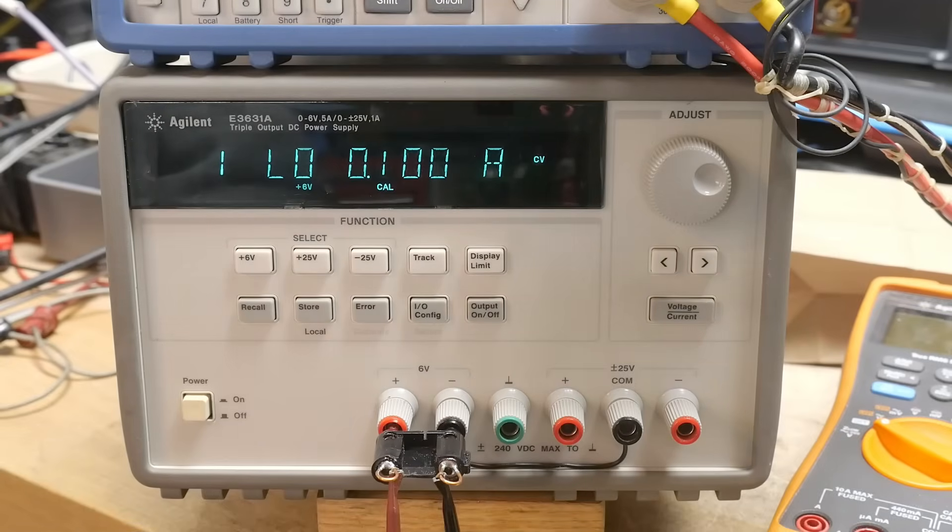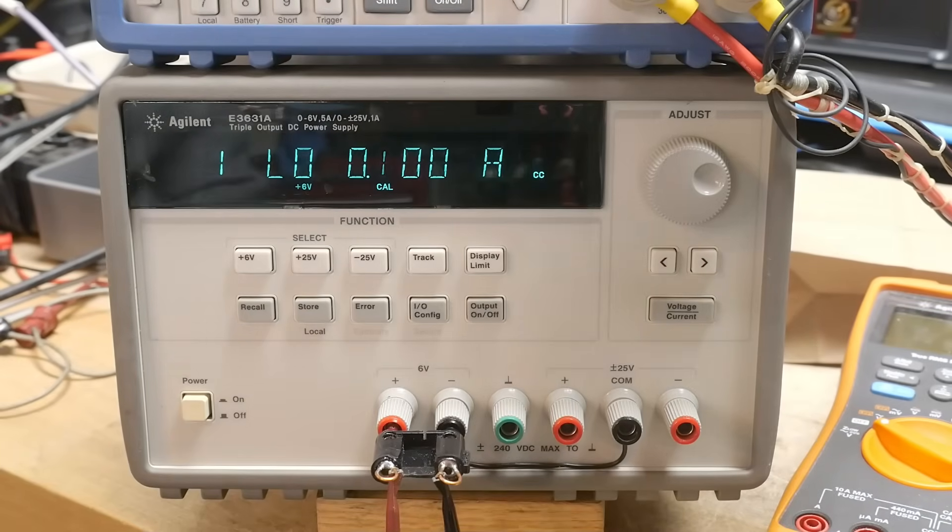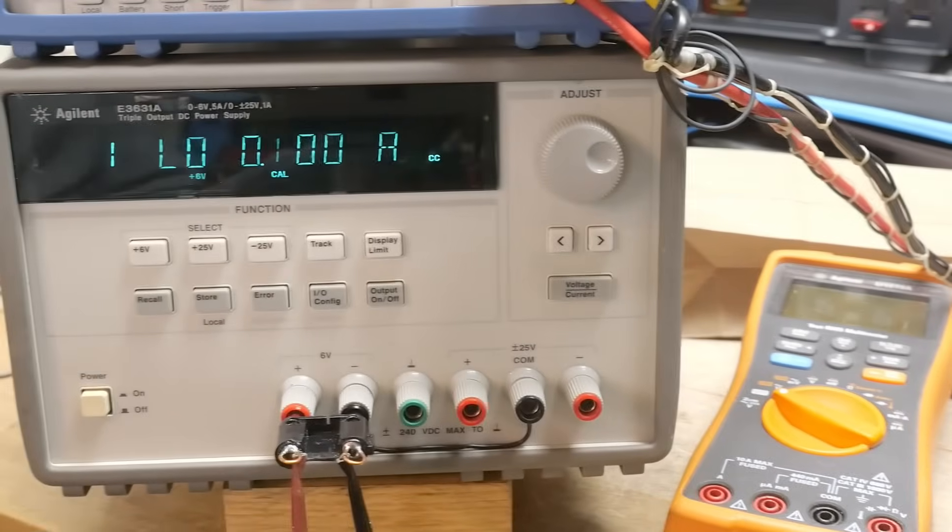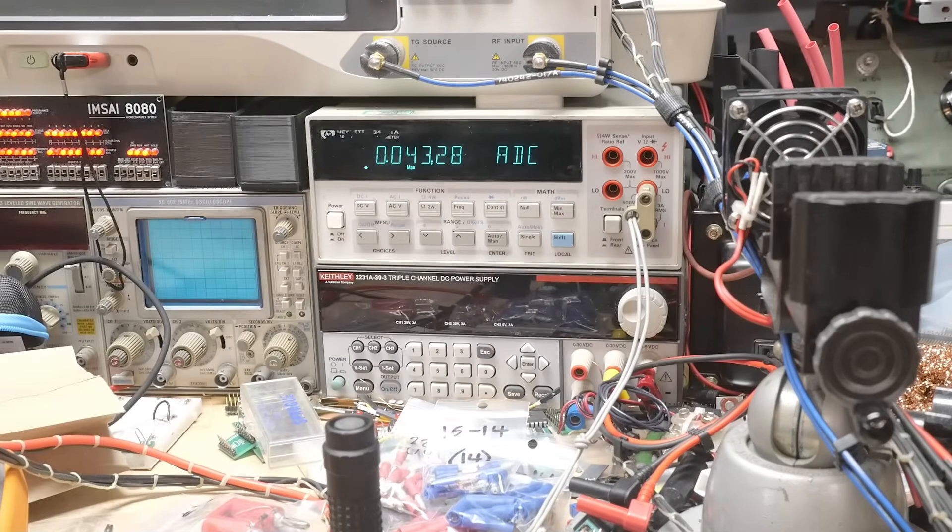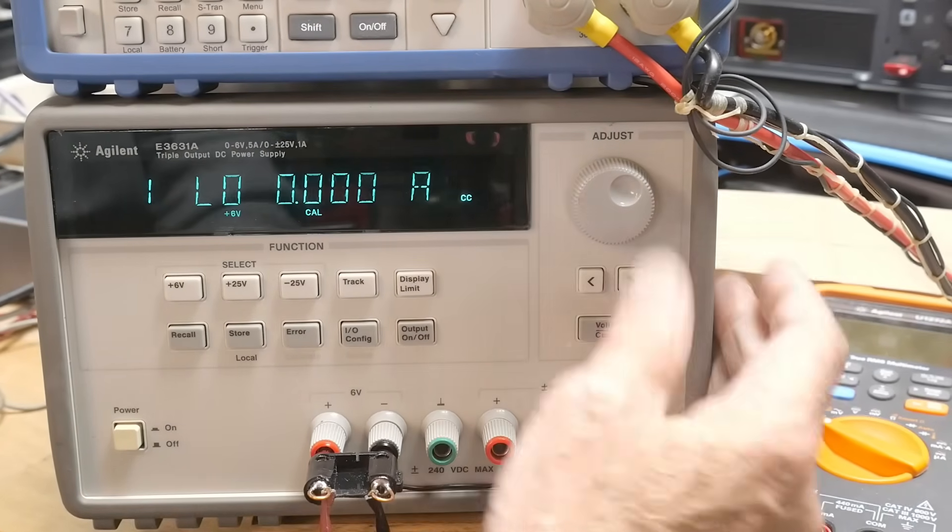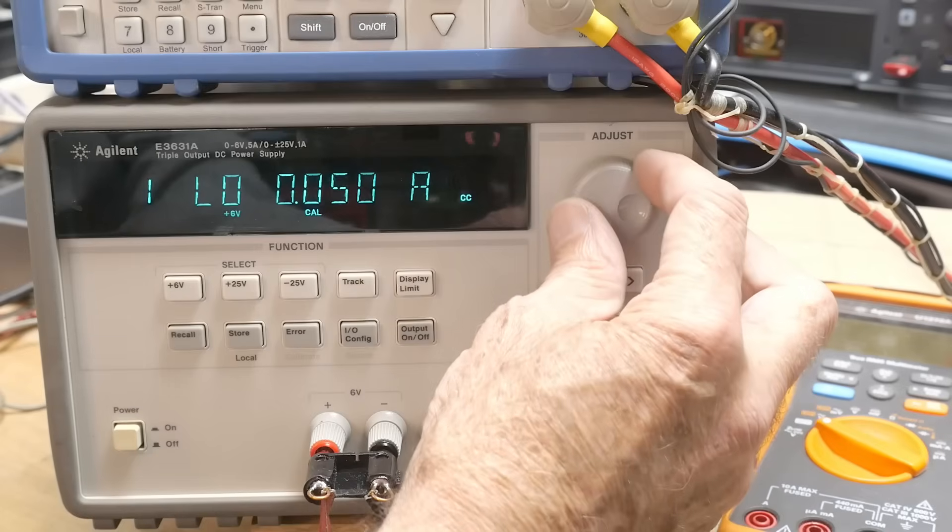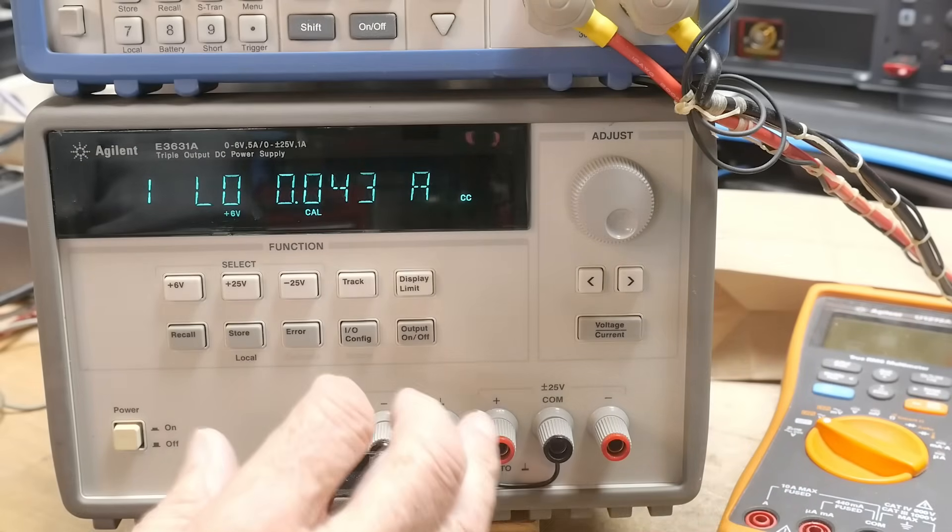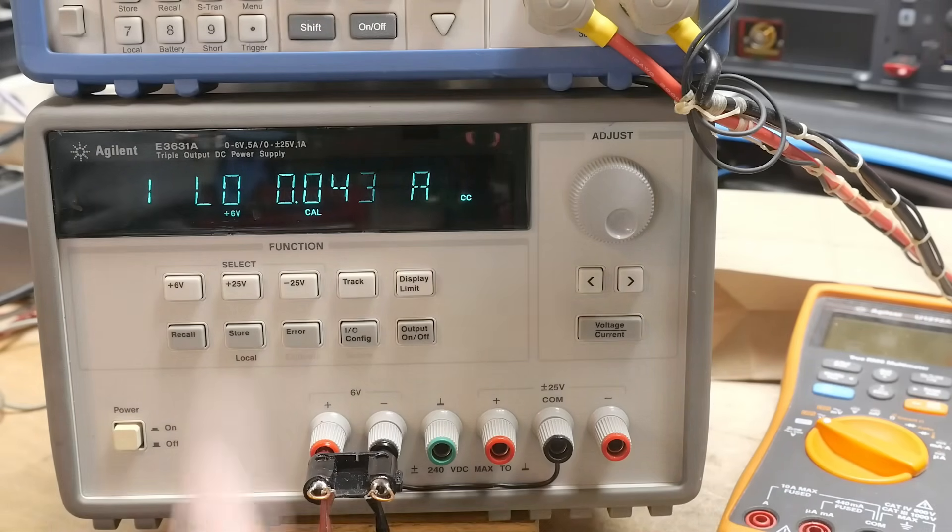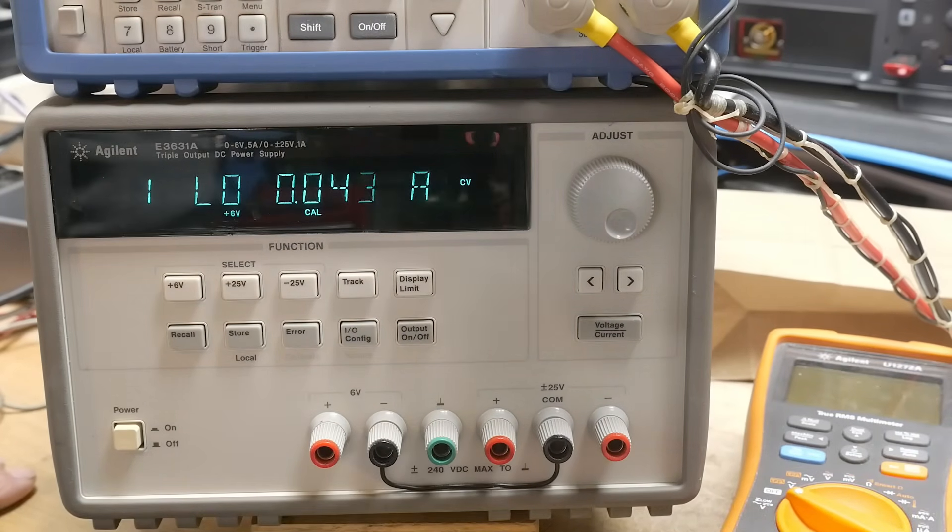Now it's going to output current. I'm going to have to reach around the camera here. I've set my meter over there to current. So it's a hundred milliamps and we're actually outputting 0.043. We're actually outputting instead of a hundred, we're outputting 43. So in order for me not to make a mistake, I'm going to do a manual range on this. So it's 043. So we're going to type that in here. Now I don't want to push the next button because it'll blow up my meter because it's going to go to lots of amps.